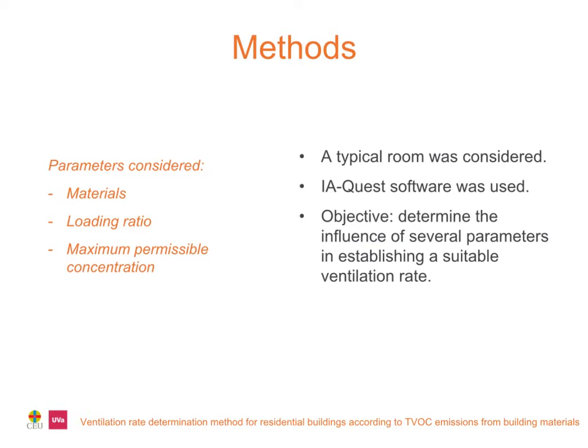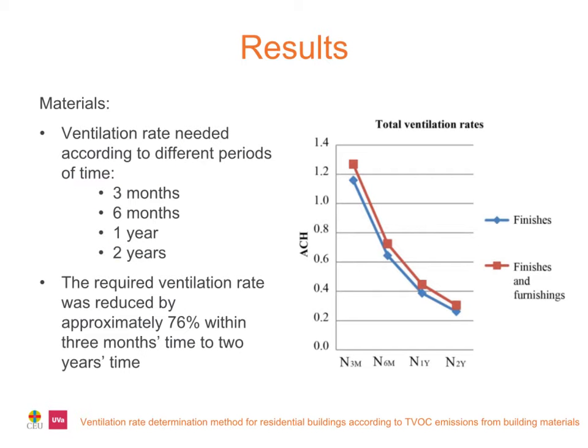A typical room was considered and several emission sources were introduced using the database included in the IA-Quest software to achieve the main objective of this study, which is to show the influence of several parameters in establishing a suitable ventilation rate. These parameters are the materials, which are the indoor pollution emission sources, the loading ratio, which is the ratio between the surface of the emission source and the volume of the room, and the maximum permissible concentration. The image shows the ventilation rate needed according to different periods of time since the application of the materials in the indoor space.